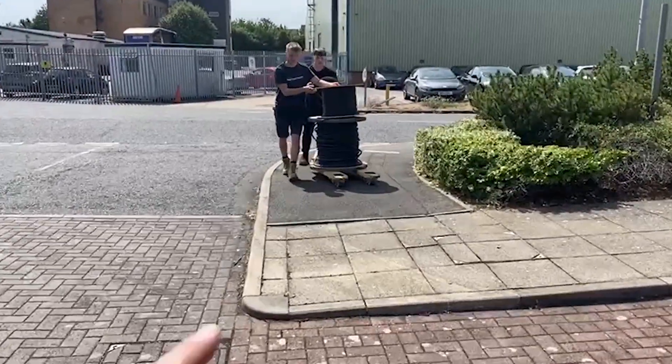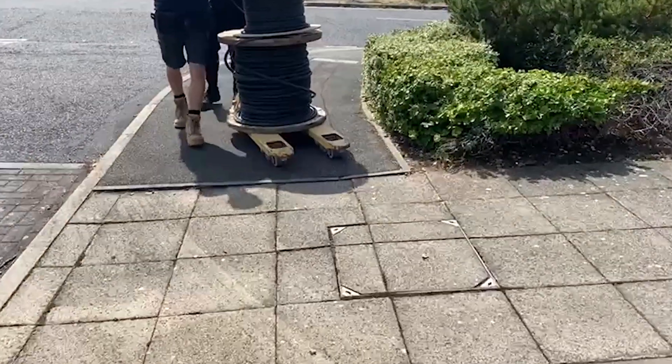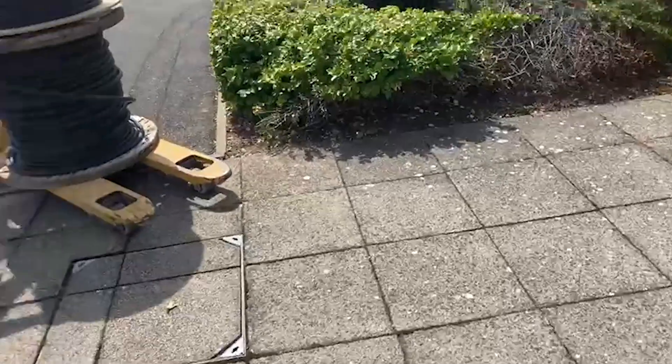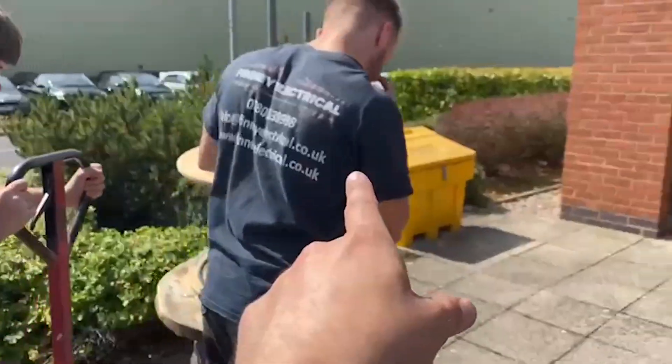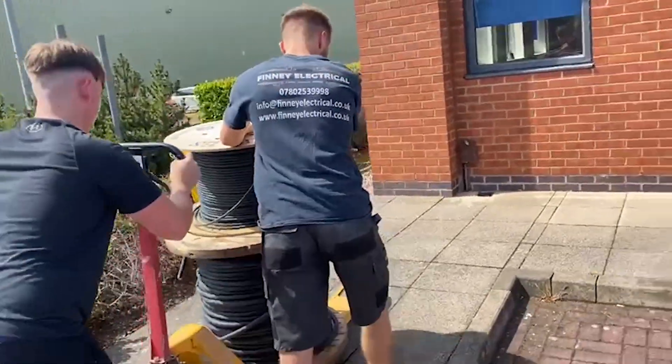That's a 5-core 6mm cable. We've got an armored cable — 5-core — which is rated the same as the cable, so you can run them both next to each other. You can get armored cable rated to do that, which is quite good. If not, we'd have to have separate ducts for them.